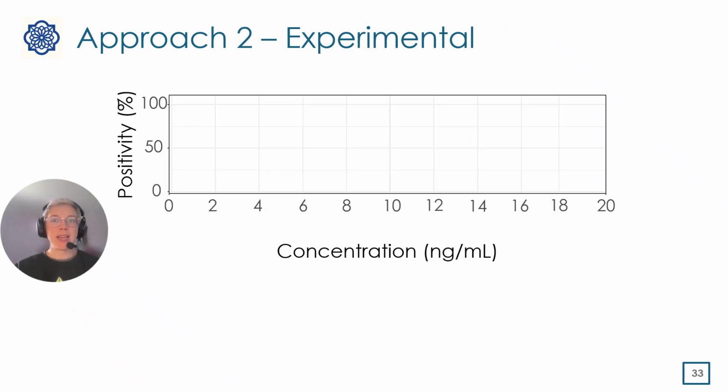First, we can use the experimental route, a bit like you would spike and analyze samples of decreasing concentrations to estimate the LOD. Well, you could spike samples at different concentrations around your threshold and analyze them to see if they get correctly classified or not. Mind you, if you want to estimate the proportion of false results at these different concentrations, you need at least 10 replicates for each level to get somewhere, and we'll get back to that later.